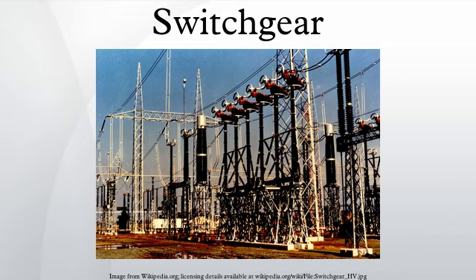Gas circuit breakers sometimes stretch the arc using a magnetic field, and then rely upon the dielectric strength of the SF6 gas to quench the stretched arc. Hybrid. A hybrid switchgear is one that combines the components of traditional air-insulated switchgear and SF6 gas-insulated switchgear technologies. It is characterized by a compact and modular design, which encompasses several different functions in one module. Vacuum circuit breakers with vacuum interrupters have minimal arcing characteristics, as there is nothing to ionize other than the contact material, so the arc quenches when it is stretched by a small amount.